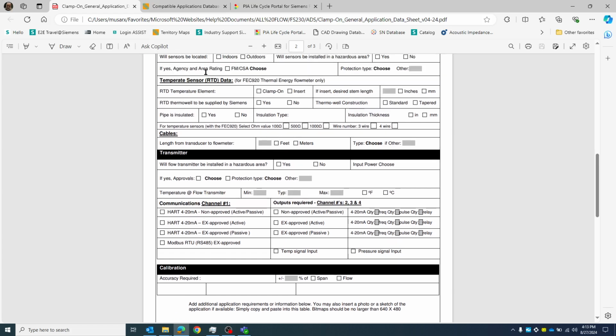The RTD information is less critical because most of the time there will be no RTD or temperature sensor for standard liquids. For hydrocarbons and gases, there certainly will be, but for water and other liquids, ordinarily there would not be, unless this meter was being paired up with an energy calculator, such as an FEC 920. Cables, we would like to know what the distance is between the transmitter and the sensors ultimately, and what type of cables. You can put down here armored if they definitely need armored cables. Otherwise, we will be supplying submersible cables.